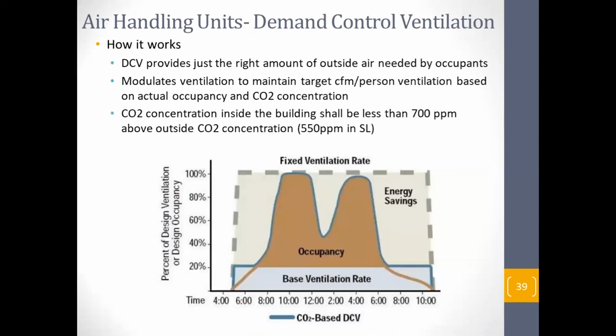And now this one is very relevant: demand control ventilation. In older buildings, you may not have CO2 sensors everywhere, but in modern, new buildings, I think we should have CO2 sensors. So rather than just fixing our air supply based on particular ambient conditions and the number of occupants, we can fix the ventilation based on the actual CO2 level.